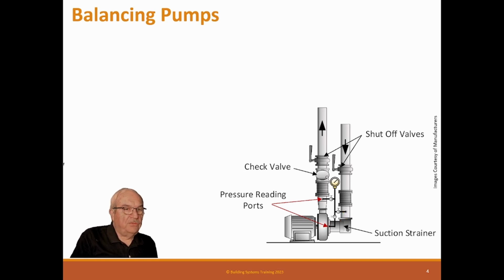So if they have two gauges, what we normally do is take one gauge off, if you're using gauges, and use it in both places. That way we take away any discrepancy in calibration between the gauges. But more than likely, you will hook up your electronic gauge to this port and then use these headers as required, and you'll only have one gauge that way.